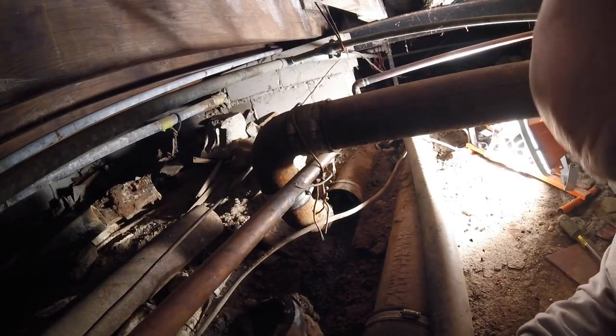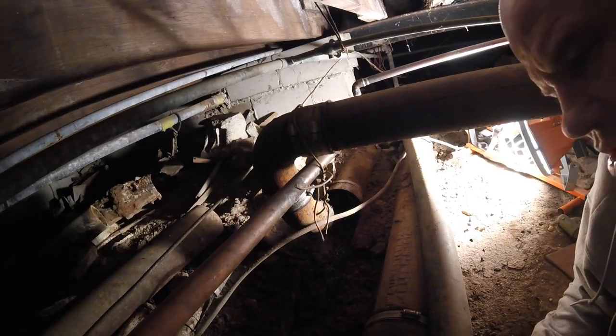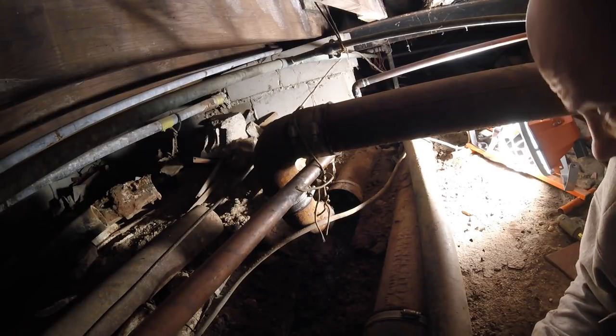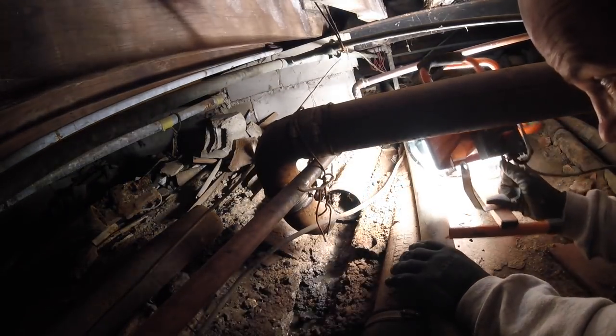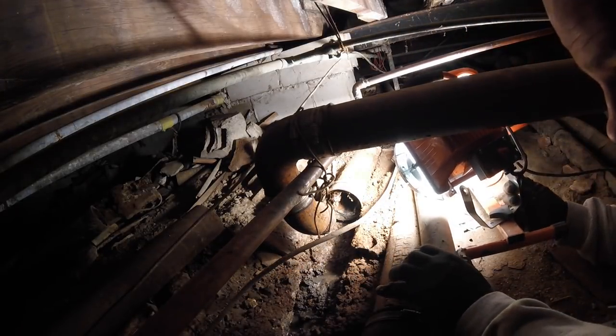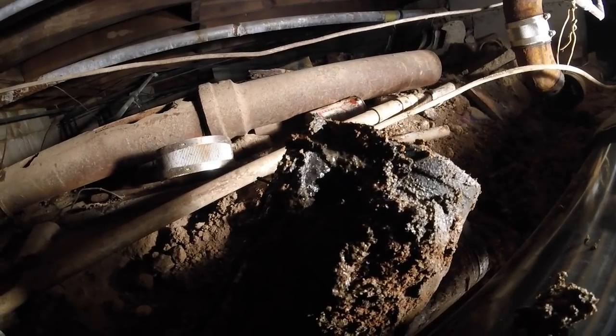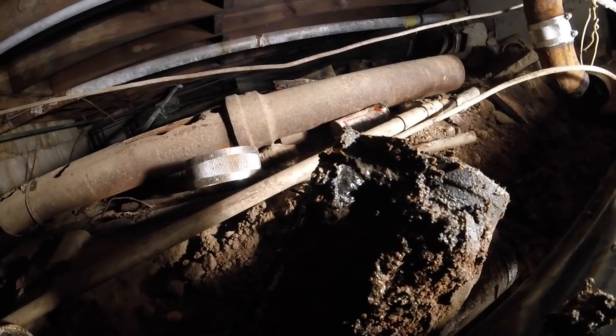We're getting up close and personal with Chuck B here. Chuck B, here's why it's leaking too. This is why, I'm gonna show people. Oh my God, this is disgusting. Oh my God, that pipe looks good. You gotta be kidding me. Now this 4x3 Y, which I'm not even going to pick up, is blown out the back too. So we need a 4x3 Y.